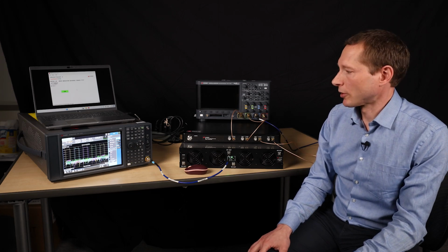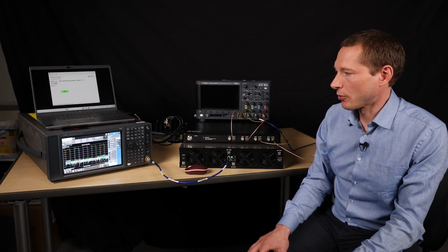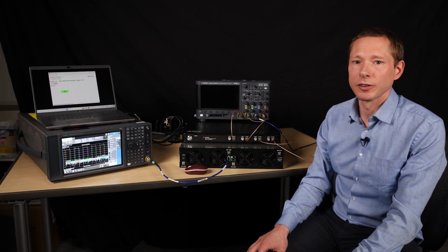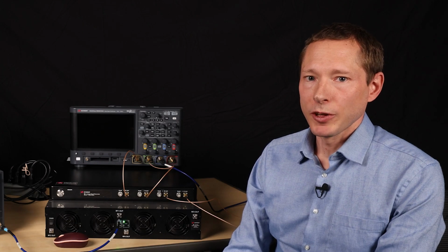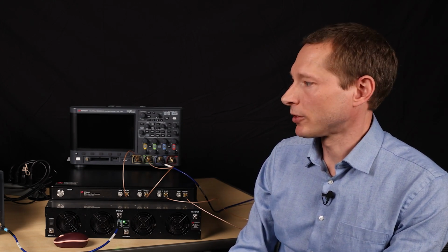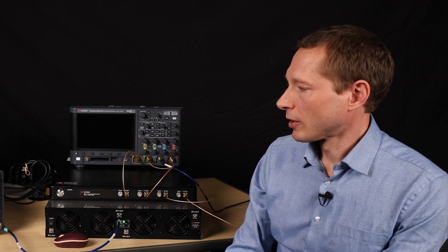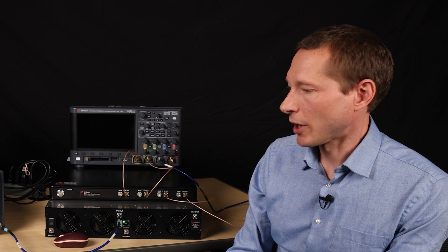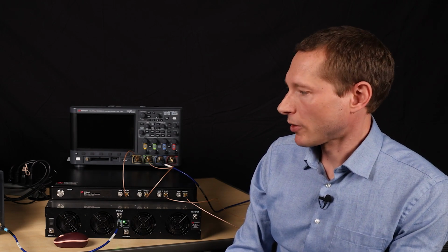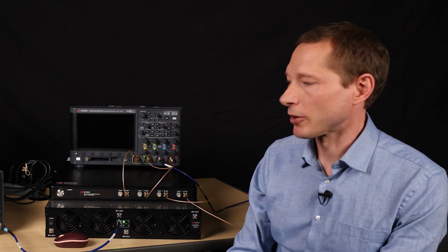For an analog signal generator, a switching time of 30 microseconds is excellent. The fast switching capabilities of the 5022 are very useful in applications like radar, where we often have to simulate scenarios with different pulses carrying different frequencies and power levels. And thanks to the fast switching capabilities, we can achieve very good pulse densities.